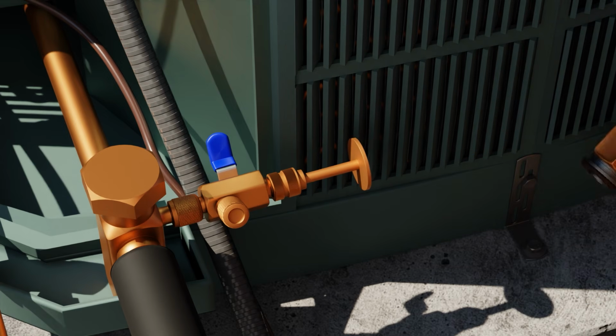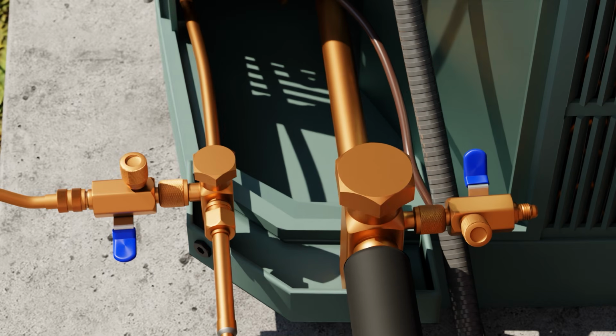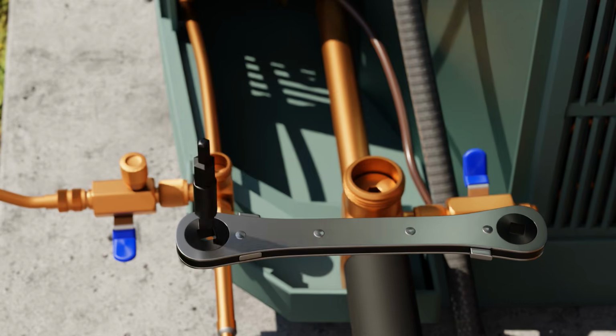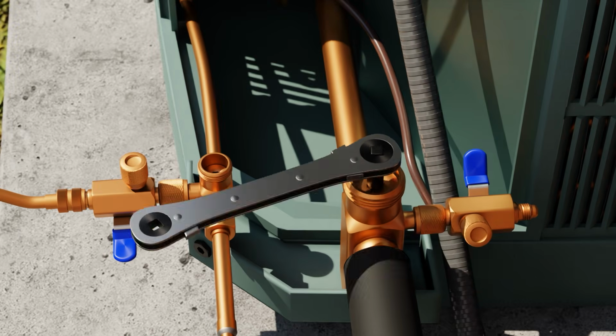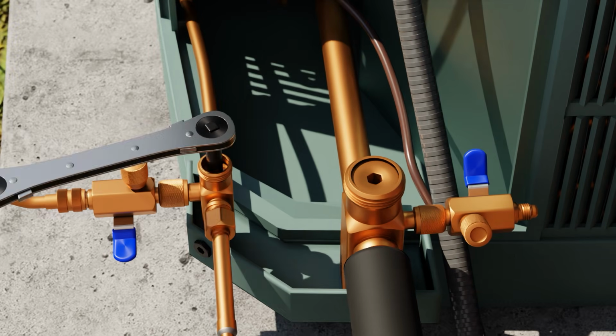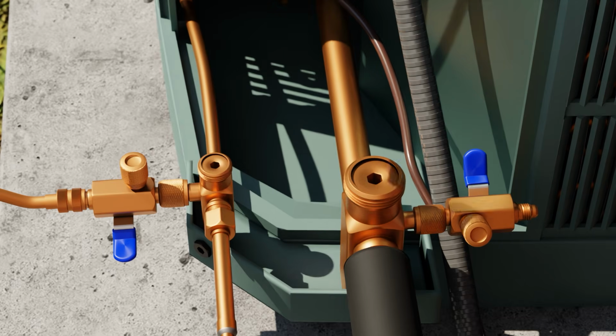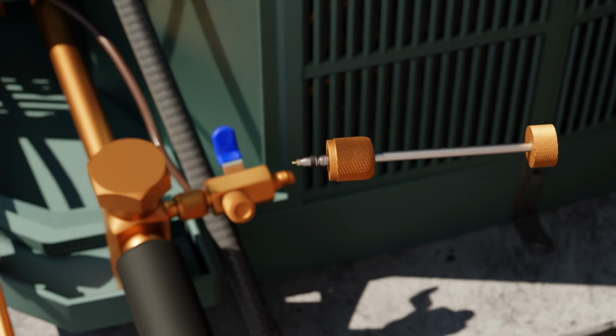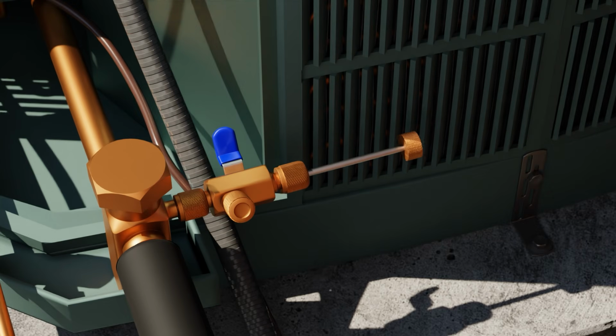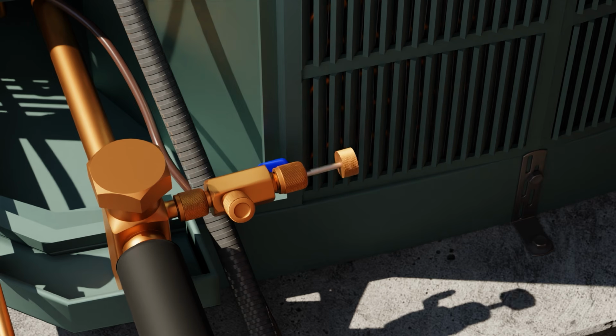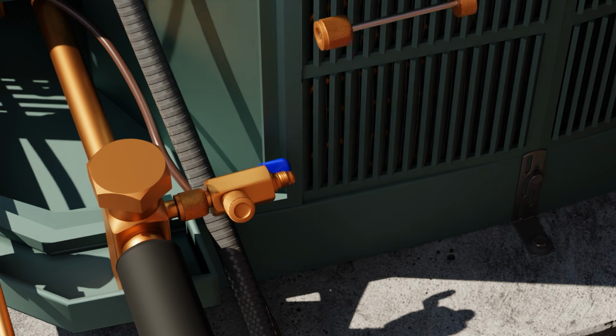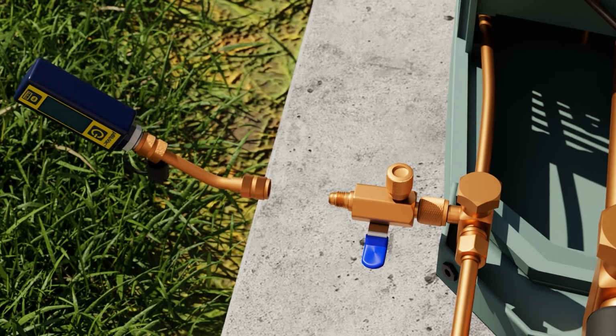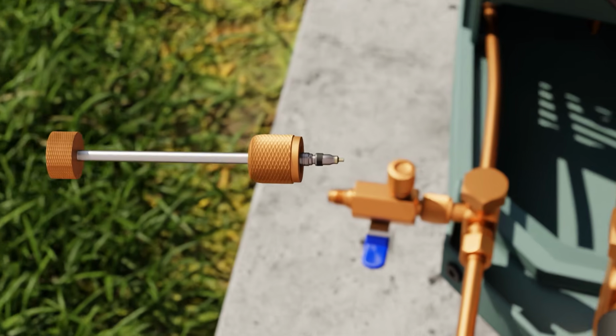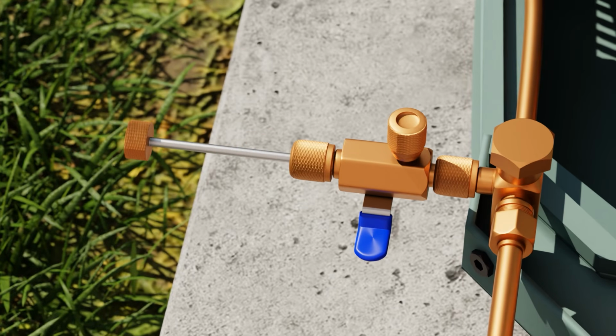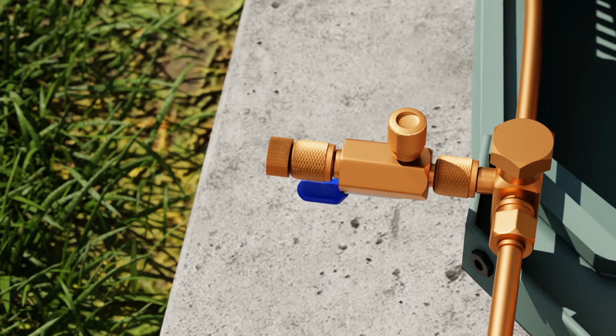Now you're ready to release the refrigerant into the lines and into the evaporator coil. First, open the suction service valve, and then the liquid valve as suggested by manufacturers. Now put your Schrader cores back in. It's important that you get this sequence correct. You do not put Schraders back into the system until after you have released the charge. Otherwise, you're going to ruin your vacuum. Now the charge is released and you can put your Schrader cores back in the system.